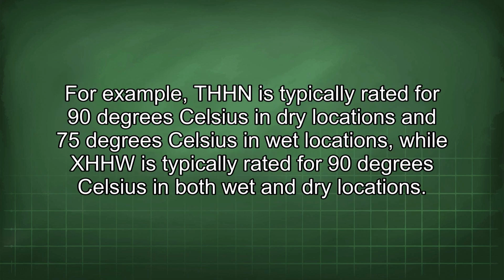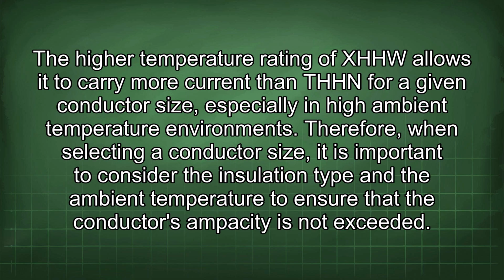For example, THHN is typically rated for 90 degrees Celsius in dry locations and 75 degrees Celsius in wet locations, while XHHW is typically rated for 90 degrees Celsius in both wet and dry locations. The higher temperature rating of XHHW allows it to carry more current than THHN for a given conductor size, especially in high ambient temperature environments. Therefore, when selecting a conductor size, it is important to consider the insulation type and the ambient temperature to ensure that the conductor's ampacity is not exceeded.